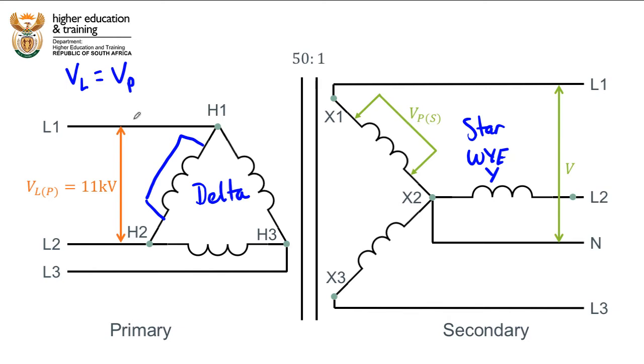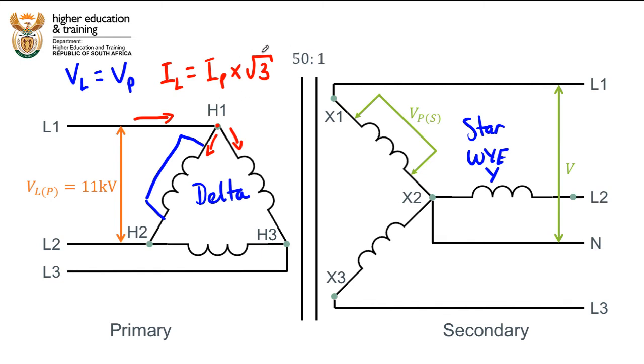Now let's look at current. If we assume current is flowing through L1, it meets a junction point and splits. So the current in the line is not the same as the current in the phase. Because the phases are separated by 120 degrees, if you work through the mathematics, the line current in a delta system equals the phase current multiplied by the square root of three. Simply remember that formula.